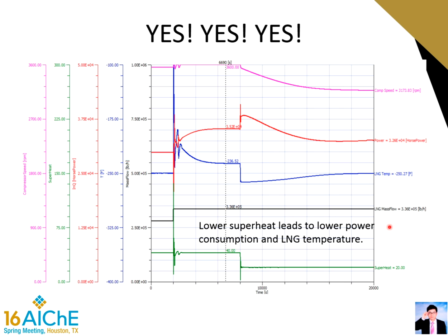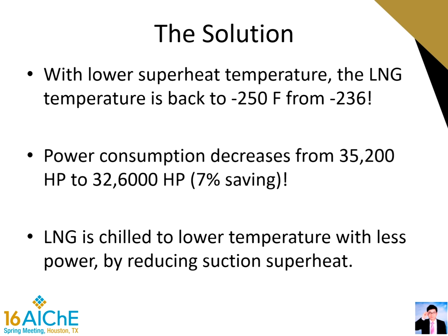Now we take a closer look at the strip chart. At time 8,000 seconds, the superheat set point is changed to 20°F. Please notice the superheat almost reaches 0°F, so on a real plant, please change the set point slowly. After a long waiting of several hours, the plant is finally stable. Compressor speed drops to about 3,200 RPM and the LNG temperature is back to negative 250°F. Power consumption drops to 32.6 thousand horsepower instead of 35.2 thousand horsepower — approximately 7% energy saving — while the product specification is still met. The LNG is chilled to the lower target temperature with less power consumption, simply by reducing the compressor suction superheat.